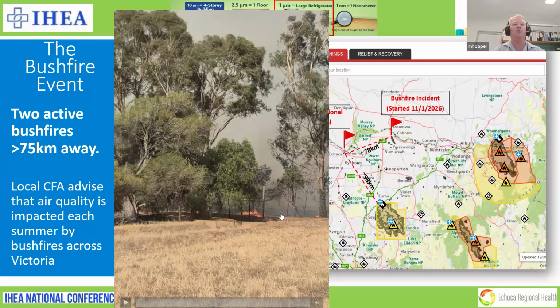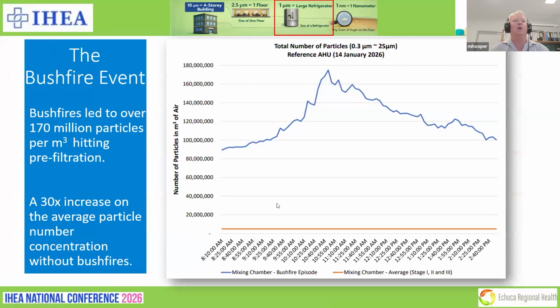That gives you an idea of just how much nasties are also floating in the air, lots of things not captured by our filters. On this particular day, 14th of January, because it takes a while for smoke to travel, when it turned up we had 170 million particles per cubic metre of the range 0.3 to 25 micron smashing into our filters. A typical day is 1 to 2 million, so we're talking about a 30-times increase on the average particle concentration.